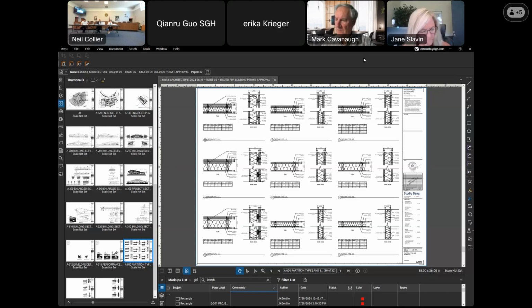I'll follow up on the standpipe to start with. Is it a dry standpipe or a wet standpipe? I would vote dry, because at some point the very end of it needs to be dry to get it out beyond the shade structure. It could be an extension of the wet part of a wet system, but my anticipation is they'd want a dry main going out there that they could plug into at a fire department connection on one side and pull water out at the far side. Fire department connection, for folks who don't run into that term every day, is the inlet on the outside of the building that the fire truck can pump water into to boost the sprinkler system or to make use of standpipes.